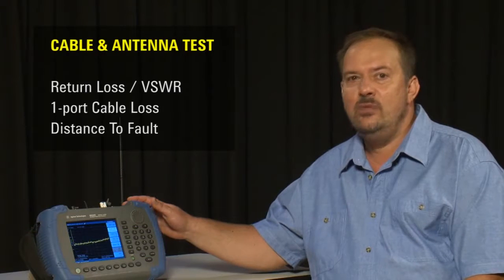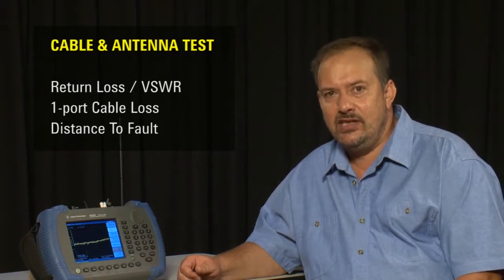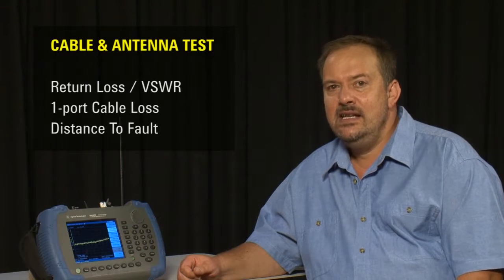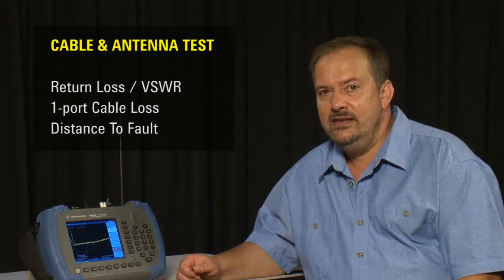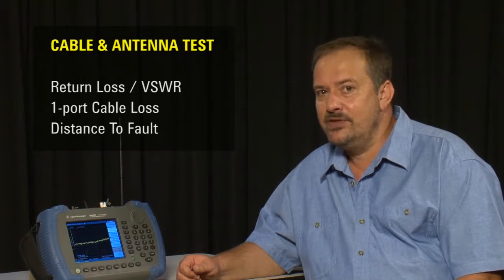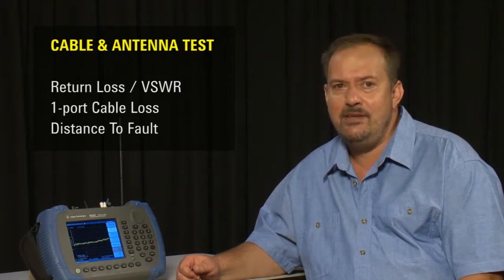If you have the Tracking Generator option installed on your HSA, then by adding the CAT option, you'll be able to measure antenna return loss and VSWR, single port cable attenuation, and Distance to Fault on cables, looking for cable breaks or damaged cables.